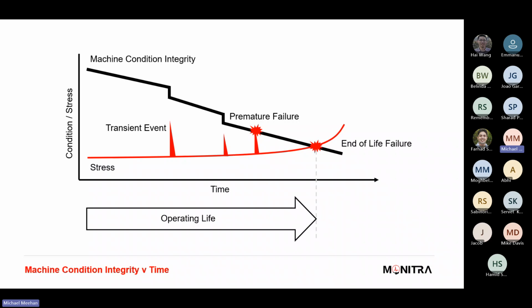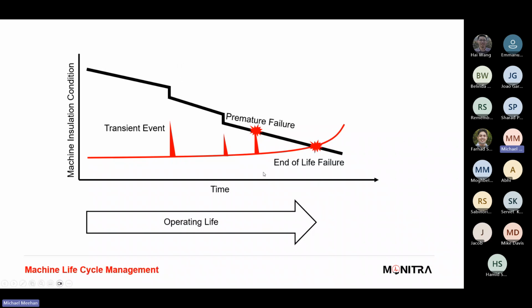Nothing was expected to be seen during that visual inspection, and a good test engineer just happened to wipe his finger internally and had a white coating on his finger. Immediately that caused concern, and we took some further covers off, and that's when we found a broken rotor bar on the rotor, and that led to further investigations. Fundamentally, the rotors were removed and replaced due to incorrect design of the rotor bars themselves. Other issues, mechanical failures, shaft misalignments, coupling misalignments, all can be factors in lessening the motor's life of operation.